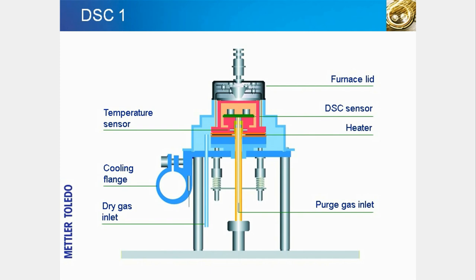When an intracooler is used, a cooling flange is placed around the oven for direct and effective cooling. For cryostats, a cooling flange is provided that holds the cooling finger of the cryostat. Depending on the temperature range of the measurement, either one or both of the gas inlets are used. The standard inlet is the purge gas inlet. If a cooling option is employed, the dry gas inlet is also used to prevent condensation from occurring inside the instrument. Samples can still be easily loaded into the furnace when the dry gas inlet is used.